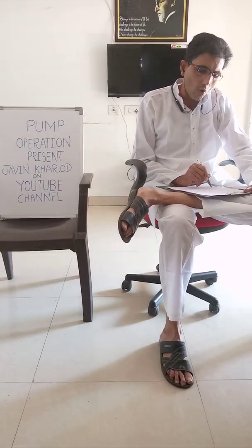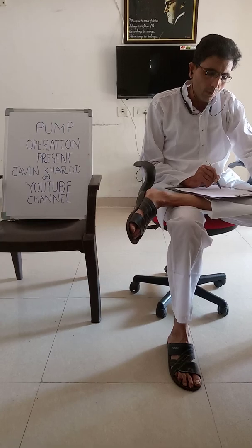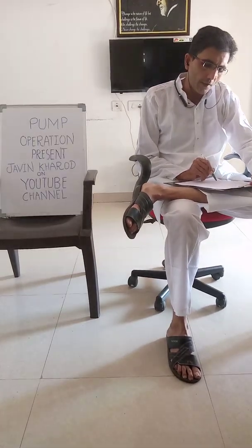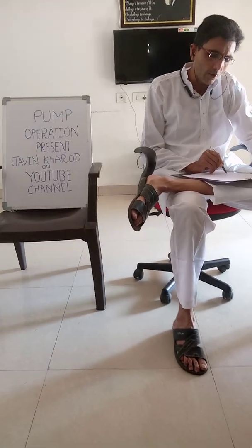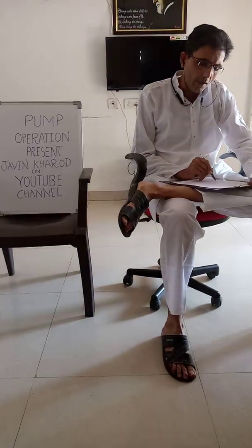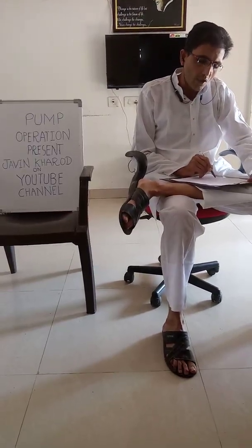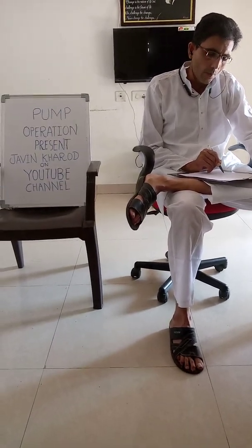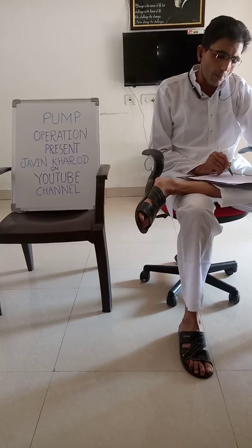Rotary pumps operating at higher speed, the fluid will cause erosion. Rotary pumps that experience erosion eventually show signs of enlarged clearance, which allows liquid to slip through and detracts from the efficiency of the pump.